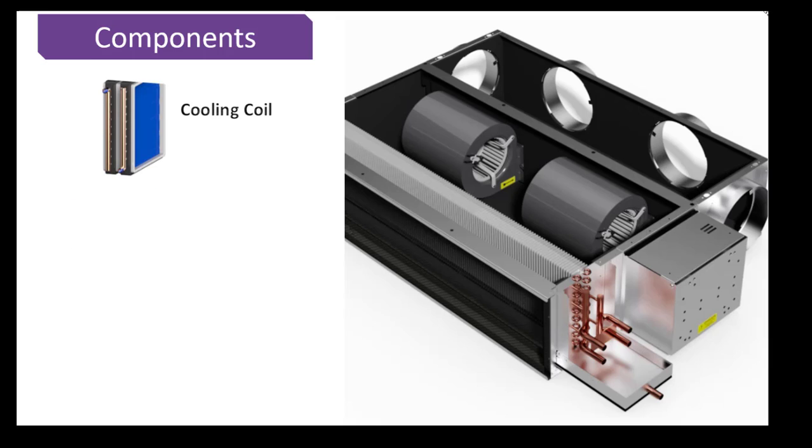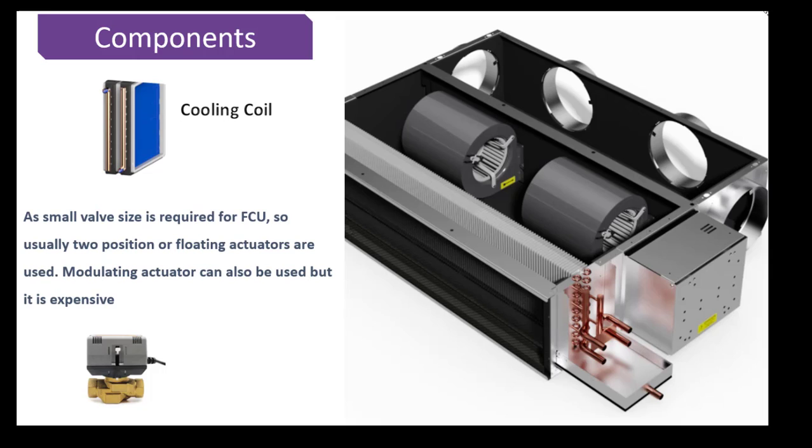Then we have a cooling coil which is used to cool down the air. A motorized valve is used to control the amount of chilled water supplied to the coil. A small valve size is required for FCU so usually two position or floating actuators are used. Modulating actuator can also be used but it is expensive. In my previous video I discussed about the valves and actuators in details so you can have a look at that video also. I will give the link in the description.